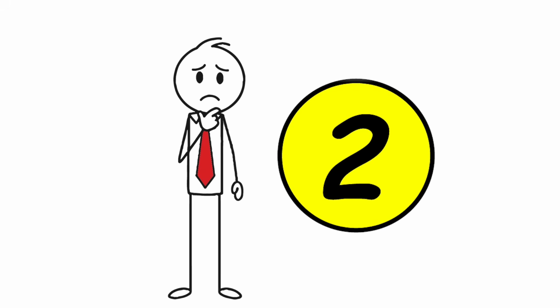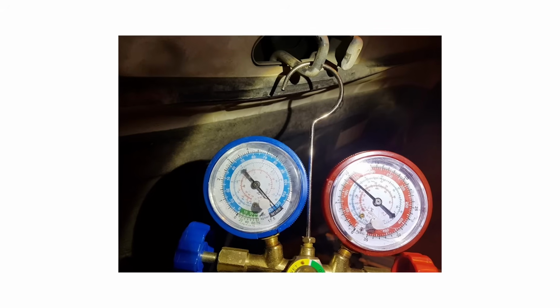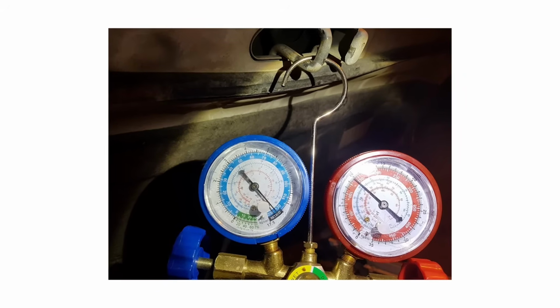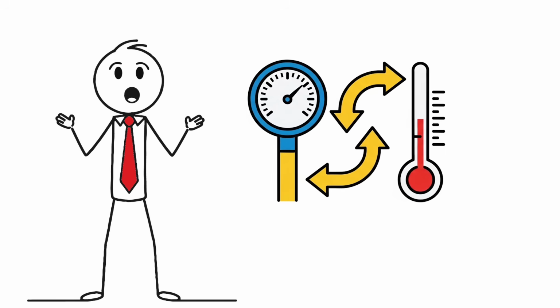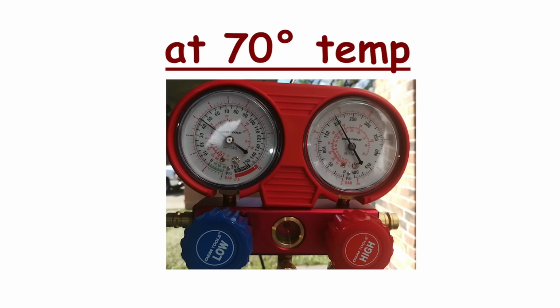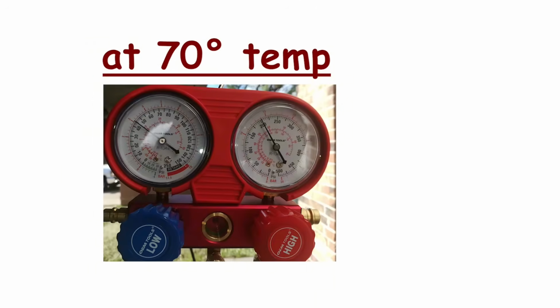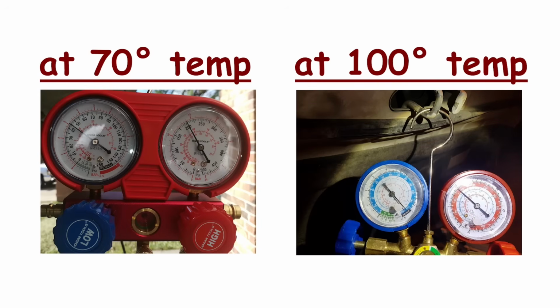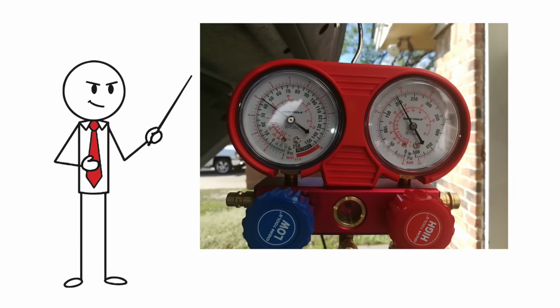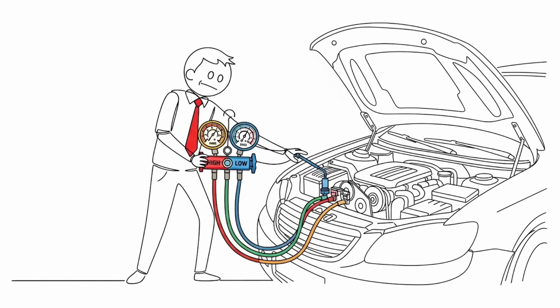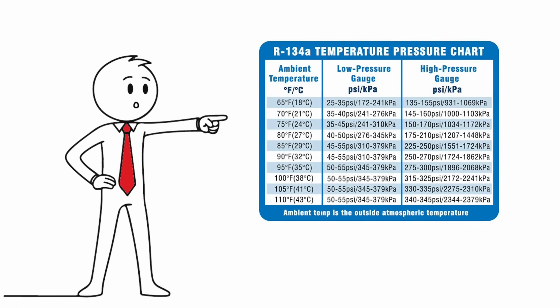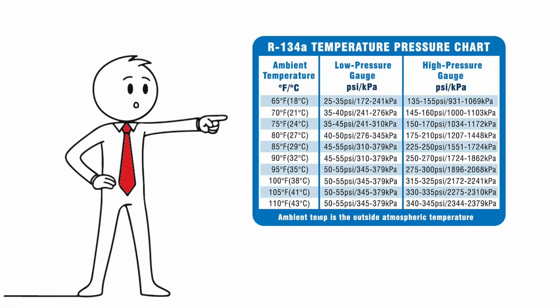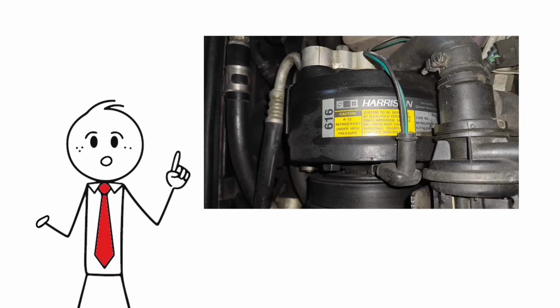Now, let's get to trick number 2, and this is where a lot of DIYers get tripped up: checking refrigerant pressure and system balance. Here is the fundamental principle of refrigeration systems. Refrigerant pressures vary predictably with temperature. This means a pressure reading that might indicate proper charge at 70 degrees could indicate severe overcharge or undercharge at 100 degrees. Professional refrigerant service requires using gauge sets to measure both high side and low side pressures simultaneously, then comparing these readings to expected values based on current temperature and the specific refrigerant type in your system.